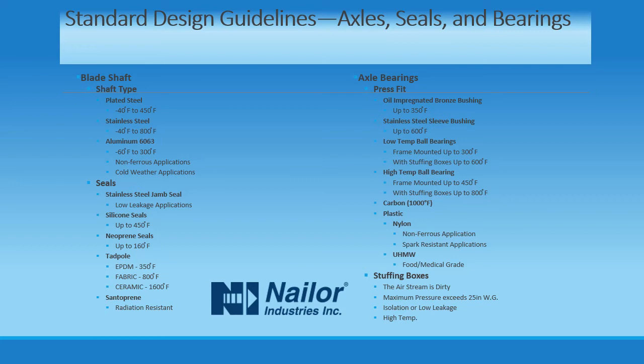We have worked with plastic bearings in applications requiring spark-resistant dampers, and UHMW polyethylene for food and medical applications. The most important consideration about choice of axles, seals, and bearing arrangements is that they can take a relatively small number of industrial models and effectively multiply them, allowing them to be suited to a larger number of different industrial applications.